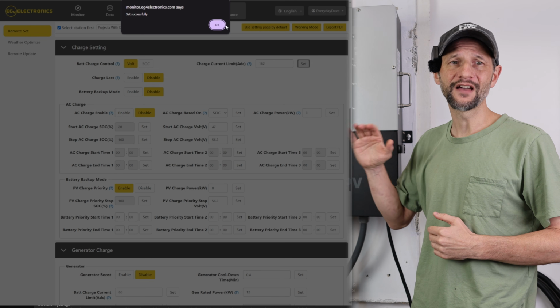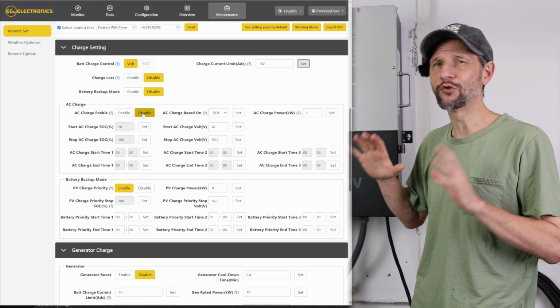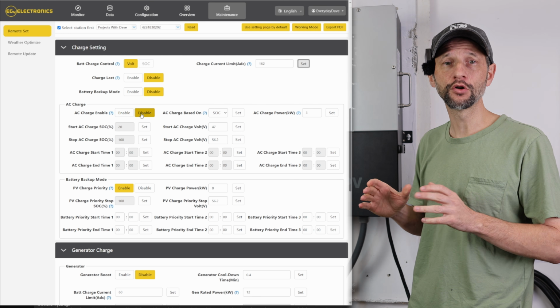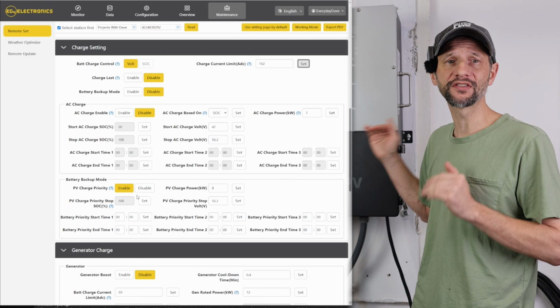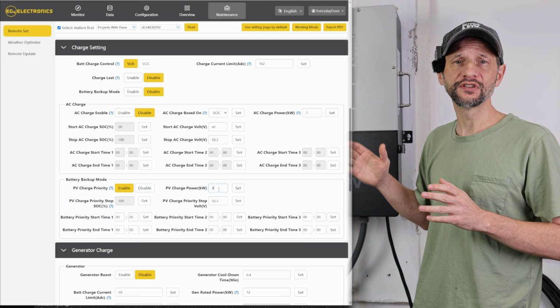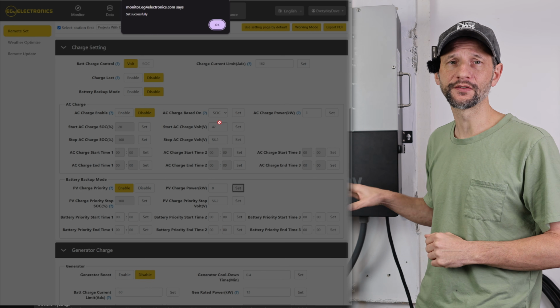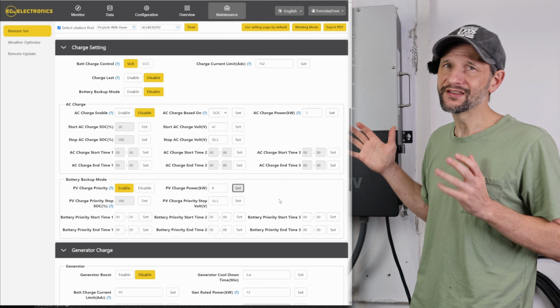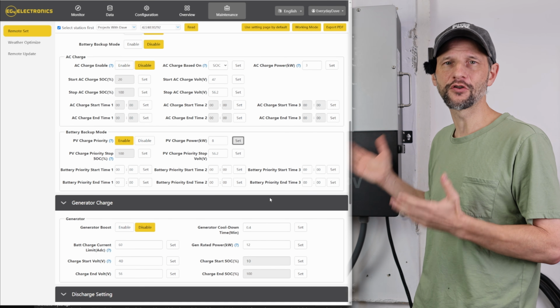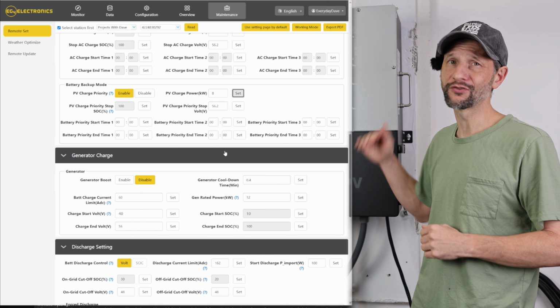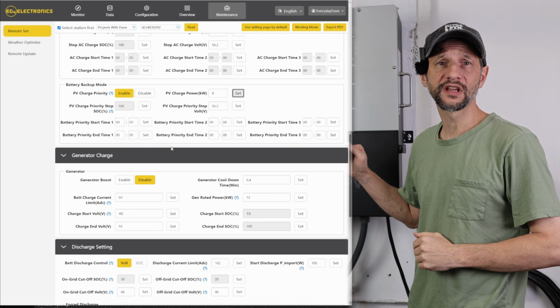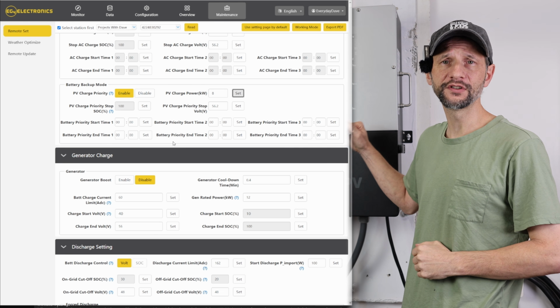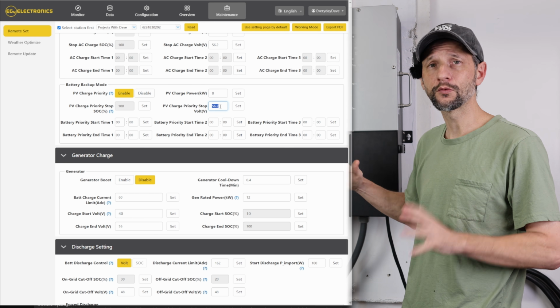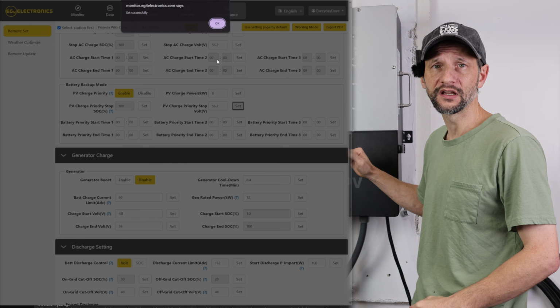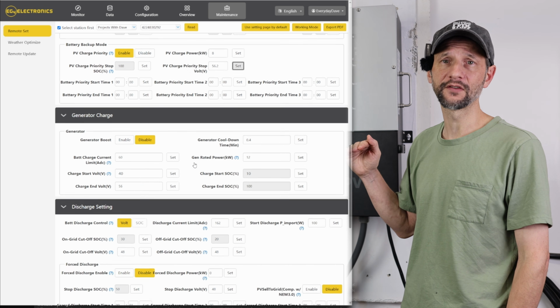In my case, I have AC charge disabled, so I will only charge from solar. In backup mode, I've enabled PV charge priority and set the limit to 8 kilowatts, which is about 0.5 C for these cells. Charging faster than 0.5 C is allowed for these cells, but if we stay at or below 0.5 C, it will increase their lifespan. So in the PV charge settings, I just set my inverter max charge voltage of 56.2 volts, and we're done with charge settings. For the discharge setting, I will once again use voltage instead of state of charge.